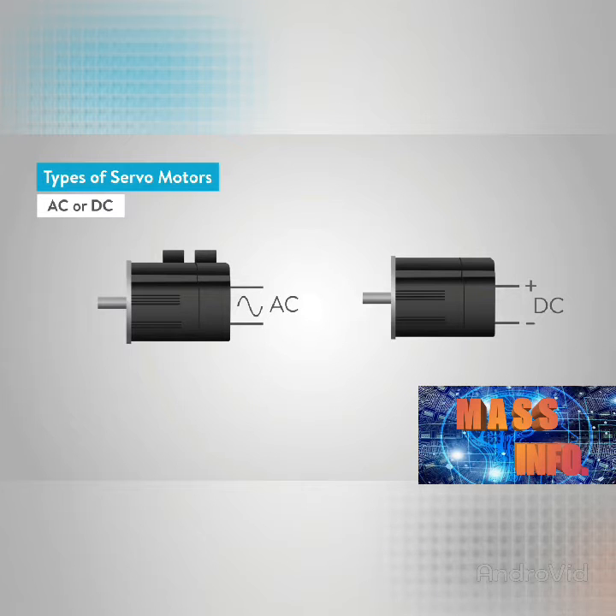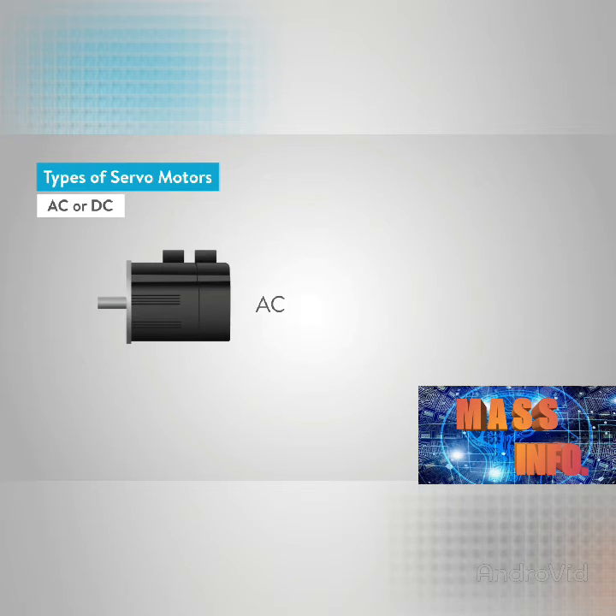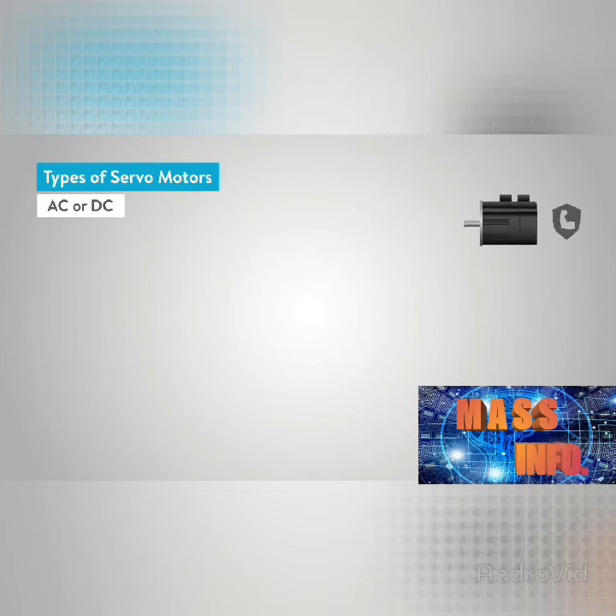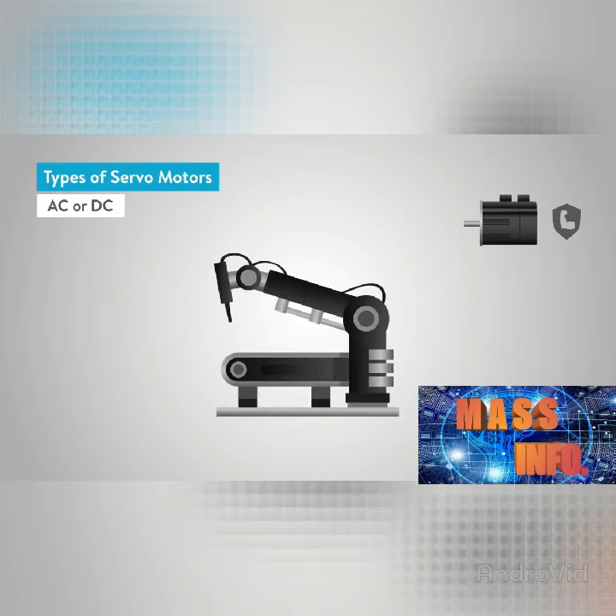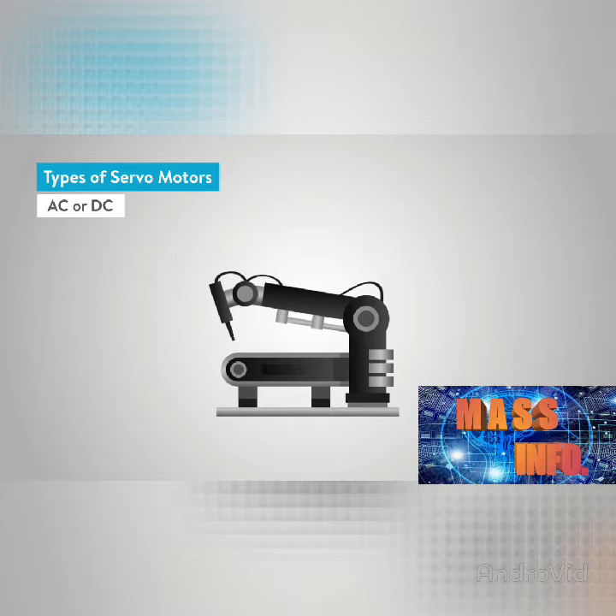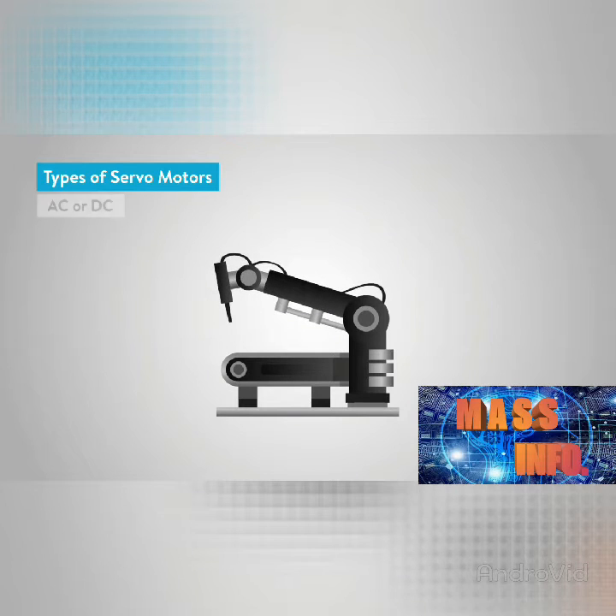In an AC motor, speed is determined by the frequency of the applied voltage and the number of magnetic poles. While both AC and DC motors are used in servo systems, AC motors will withstand higher current and are more commonly used in servo applications such as with robots, inline manufacturing, and other industrial applications where high repetitions and high precision are required.